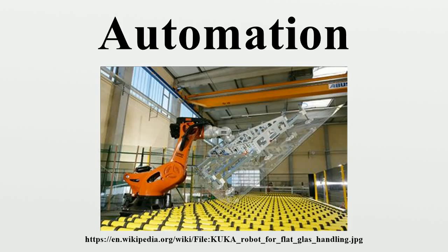Actuators are typically a better choice for intermittently creating a limited range of movement for a mechanical component, such as moving various mechanical arms, opening or closing valves, raising heavy press rolls, applying pressure to presses. Computer control. Computers can perform both sequential control and feedback control, and typically a single computer will do both in an industrial application. Programmable logic controllers are a type of special-purpose microprocessor that replaced many hardware components such as timers and drum sequencers used in relay logic-type systems.